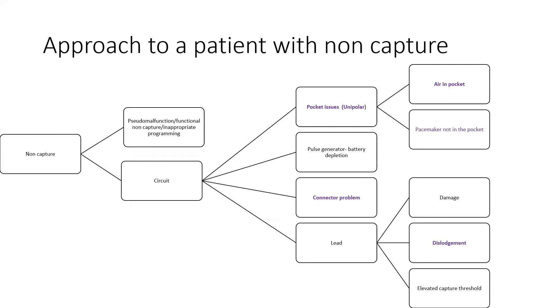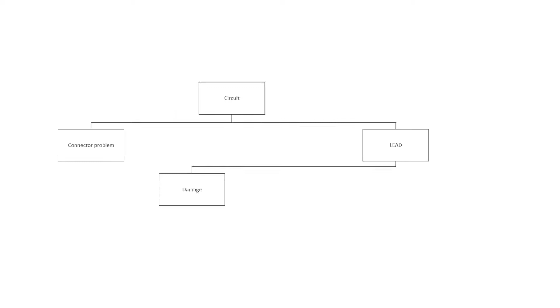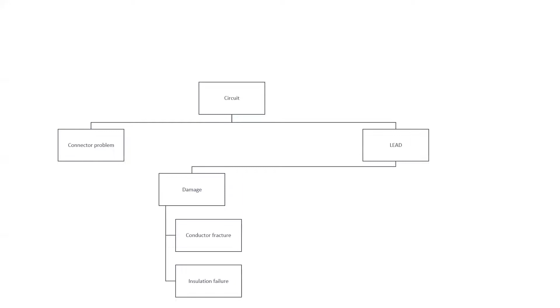The differential diagnosis in a patient with non-capture is also helped by the time of onset of non-capture in relation to implantation of the device and the lead system. So immediately after the implantation of pacemaker, the issues that may be encountered are highlighted in purple here. Now, lead issues can again be divided according to etiology. For example, a lead damage may be due to a conductor fracture, which will result in rise of impedance, or an insulation failure, which will result in a decrease in impedance. Lead dislodgement may be micro or macro, or it may be due to perforation of the thin-walled RV, especially in the leads which are placed at the apex.